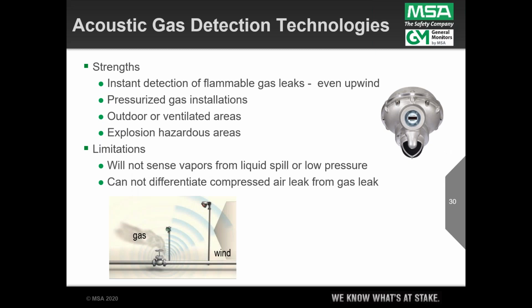In fact, here are the strengths and the limitations. It's very fast, so it can sense a pressurized gas leak even upwind of it by listening for the ultrasonic acoustic signature of that hiss, if you will, of gas. It's great for outdoor ventilated areas, explosion hazard areas, but as I mentioned, it will not sense vapors from a liquid spill or a low pressure leak, and it can't differentiate compressed air leaks from actual flammable or dangerous gas leaks. They have that same signature. But again, it suits those tough situations, and where we see most of them installed is offshore oil platforms in the North Sea and in windy areas like that.